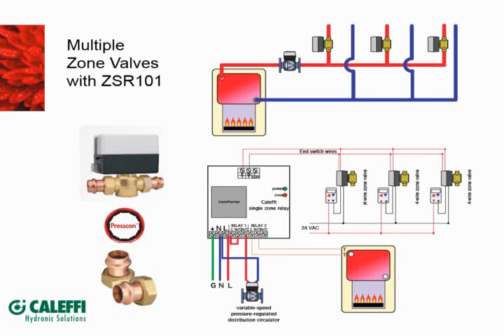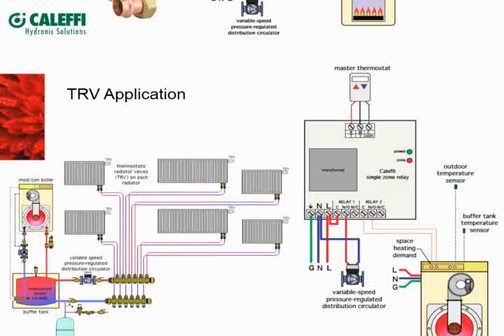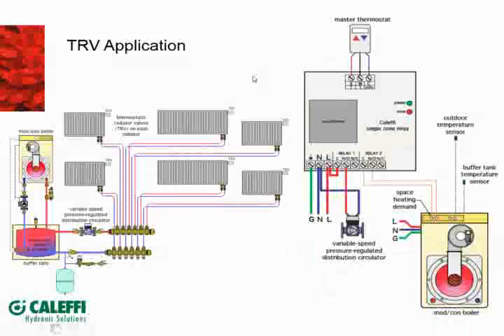And here's another application drawing, it's in our idronics 14. On the left here, we've got a Modcon boiler with a buffer tank, a variable speed pump, and then we're doing a bunch of panel radiators out here with thermostatic radiator valves on each one of them. So the idea is to have a master thermostat, and that one's going to be set to a little higher set point. So as soon as the temperature in the house drops below that master thermostat, it's going to initiate a demand to the relay box. So the relay box then will fire up the TT contacts on the boiler, and the boiler then is going to look at the outside air temperature, and it's going to adjust the temperature inside the buffer tank to meet that desired temperature based off of the outside air reset curve.